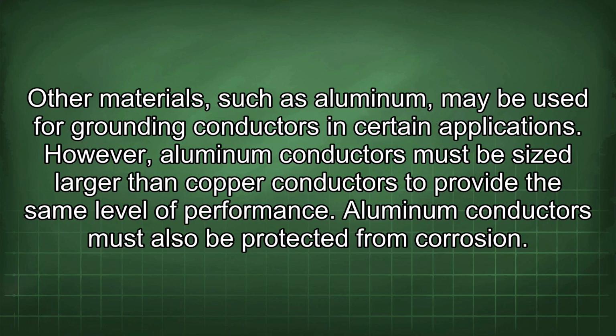Other materials, such as aluminum, may be used for grounding conductors in certain applications. However, aluminum conductors must be sized larger than copper conductors to provide the same level of performance. Aluminum conductors must also be protected from corrosion.